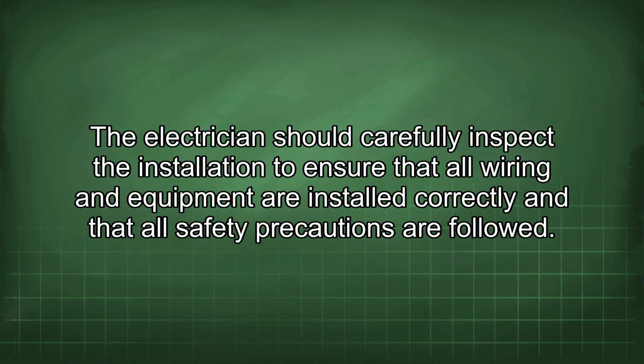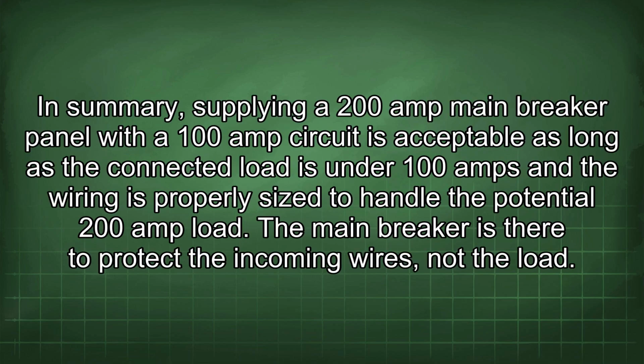The electrician should carefully inspect the installation to ensure that all wiring and equipment are installed correctly and that all safety precautions are followed. In summary, supplying a 200 amp main breaker panel with a 100 amp circuit is acceptable as long as the connected load is under 100 amps and the wiring is properly sized to handle the potential 200 amp load. The main breaker is there to protect the incoming wires, not the load.